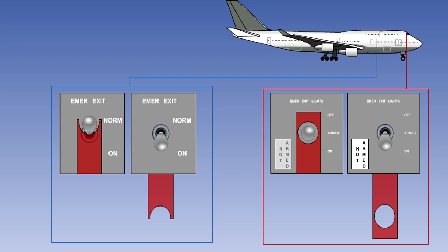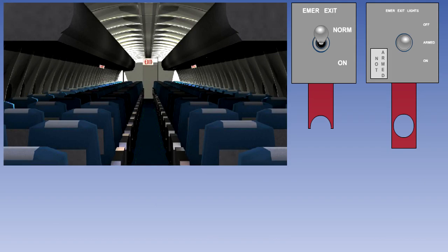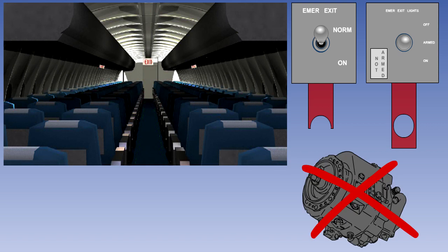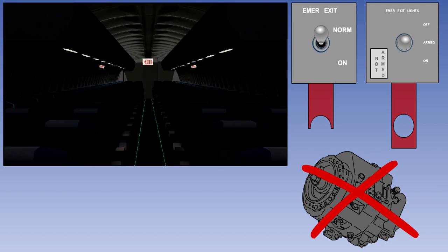The passenger cabin switch has two positions: normal and on. It is usually in the normal position. With the flight deck switch in the armed position and the cabin switch in the normal position, the emergency light control circuit is armed. It is monitoring the aircraft's essential electrical system, and provided the system is normal, the emergency lights will be extinguished. If the aircraft's essential electrical power system fails, the emergency lights will illuminate automatically.